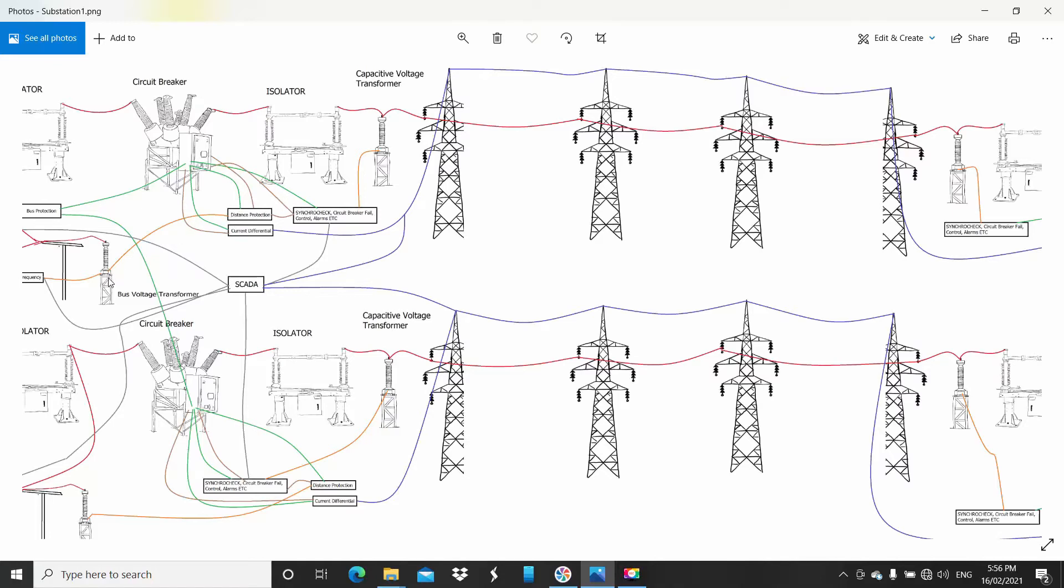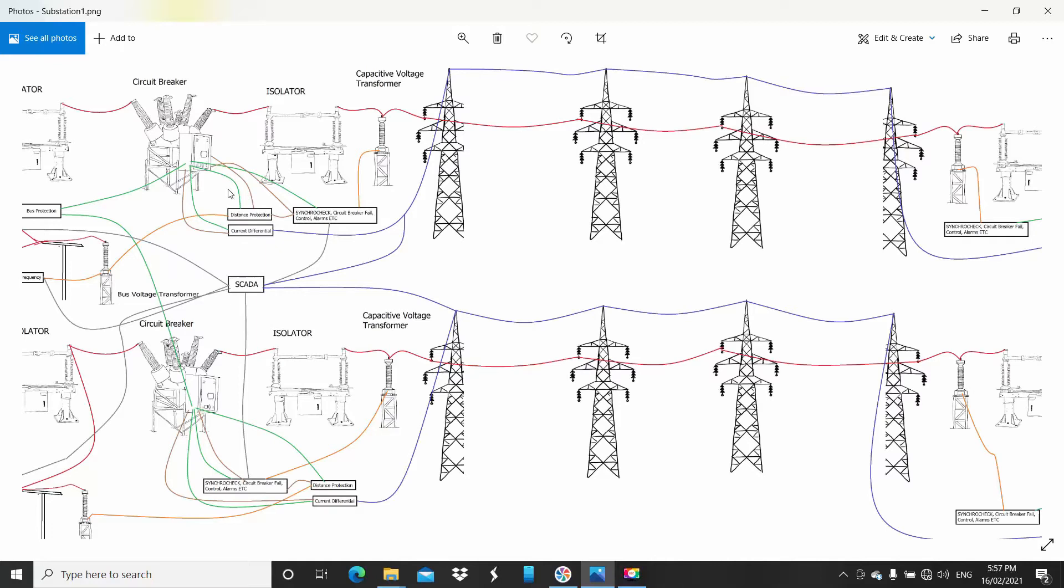The reason I've got this one from the bus is because if anything happened, I always want my voltage on that relay. If this circuit breaker was open or this isolator was open, that VT may have no volts on it. In this case, for this relay, I want volts on my relay. An impedance relay looks at the current and the volts and works out what the impedance is. When you have low current, for example the current you'd expect on the line, you'd have a really high impedance. Once you have really high current or higher than expected, you'd have a lower impedance.